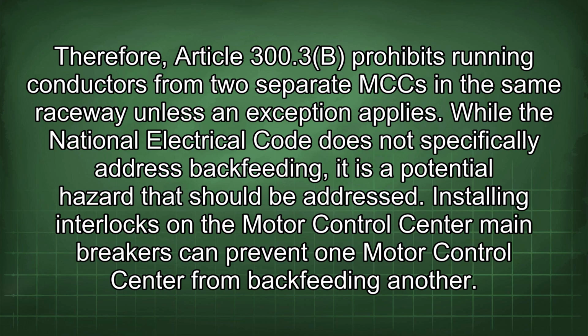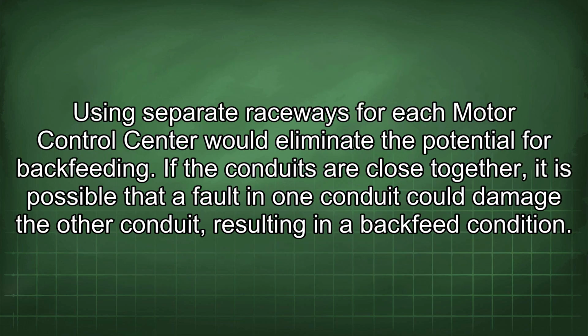While the National Electrical Code does not specifically address backfeeding, it is a potential hazard that should be addressed. Installing interlocks on the motor control center main breakers can prevent one motor control center from backfeeding another. Using separate raceways for each motor control center would eliminate the potential for backfeeding. If the conduits are close together, it is possible that a fault in one conduit could damage the other conduit, resulting in a backfeed condition.